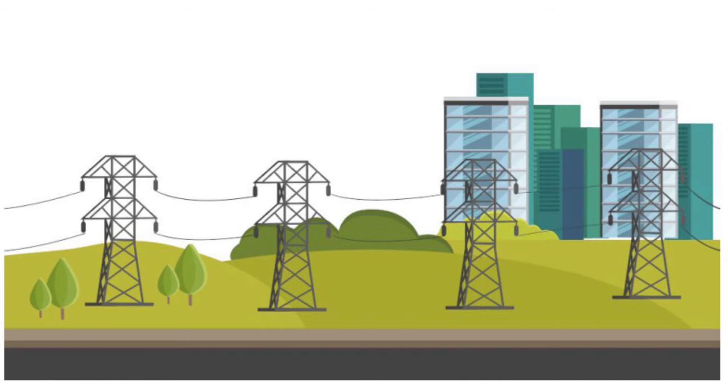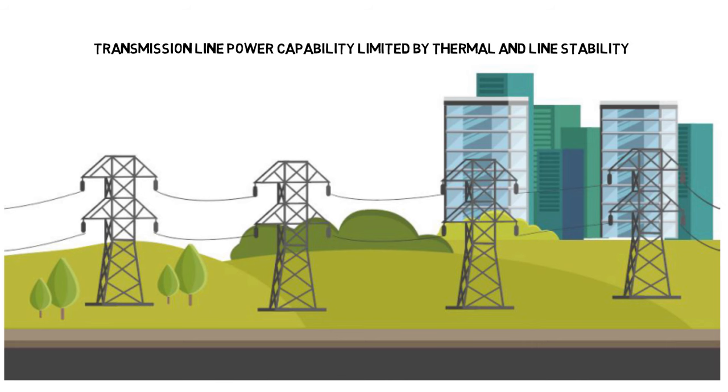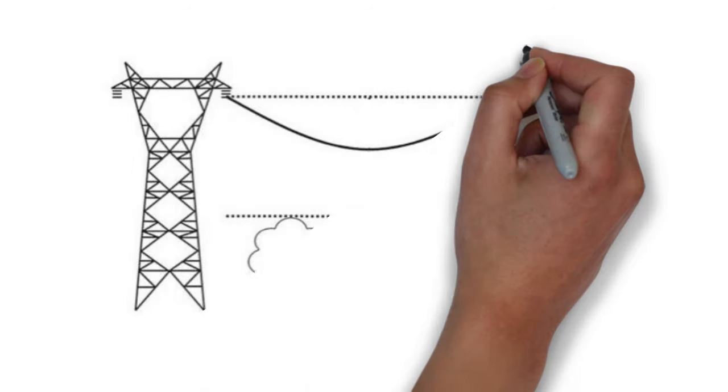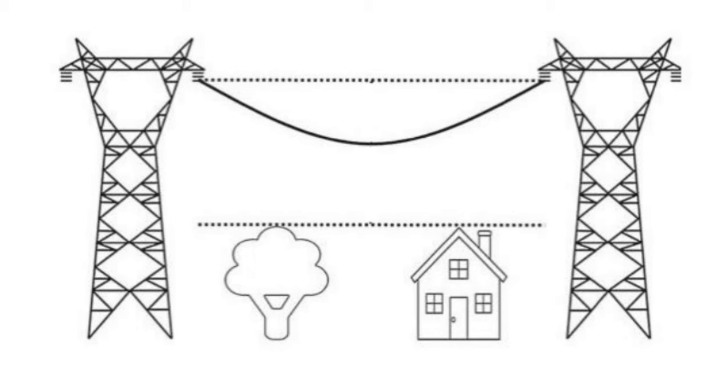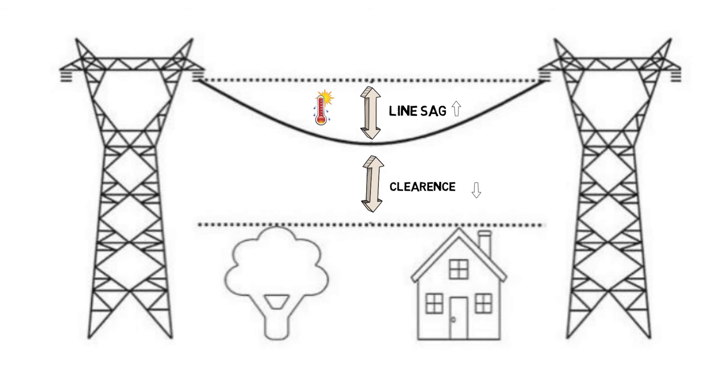Power capability of a transmission line is limited by the thermal loading and stability limit. An increase in conductor temperature caused by real power loss can stretch the conductors and increase the sag between transmission line towers consequently reducing the clearance distance.